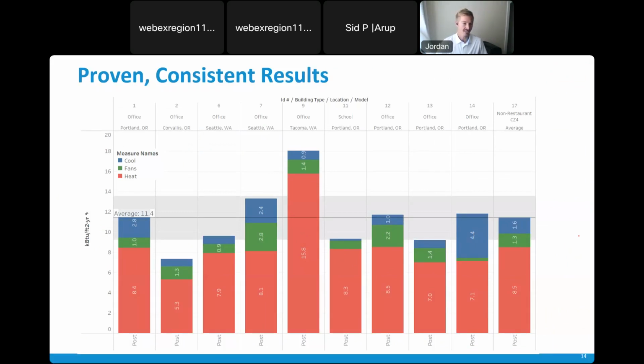So on average, the HVAC energy use intensity after converting to very high efficiency DOAS was 11.4 kBtu per square foot per year, on quite a tight band of these buildings. We threw out some of the colder climates since they're a little higher naturally with more extreme climates, but this is all buildings kind of on the I-5 corridor, Portland, Seattle, everything basically west of the Cascade Mountain Range. Offices and schools kind of didn't matter where they started, but they all finished at a very low energy use.